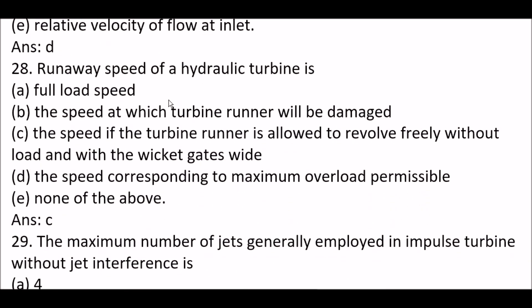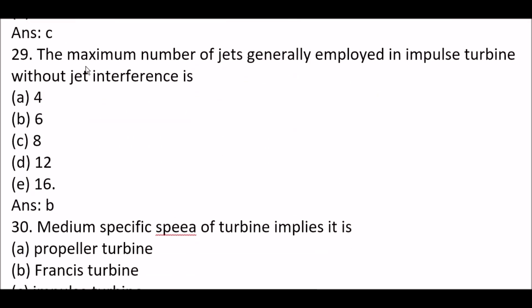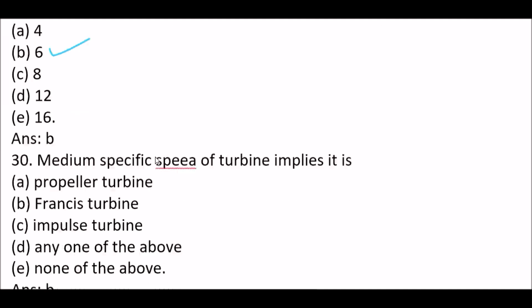Next question. Runaway speed of a hydraulic turbine is option C, the speed if the turbine runner is allowed to revolve freely without load and with the wicket gates wide. Next question. The maximum number of jets generally employed in impulse turbine without jet interference is option B, 6. So maximum number of jets generally employed in impulse turbine without jet interference is 6.